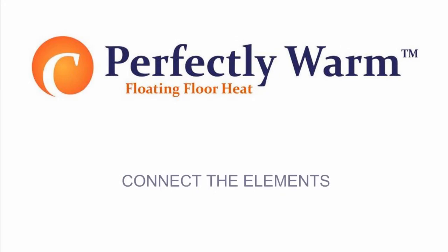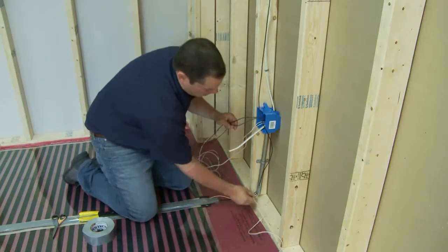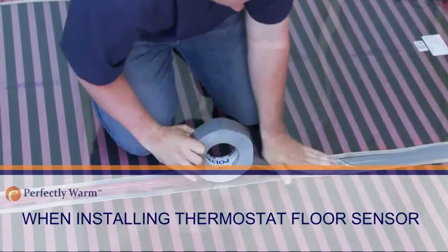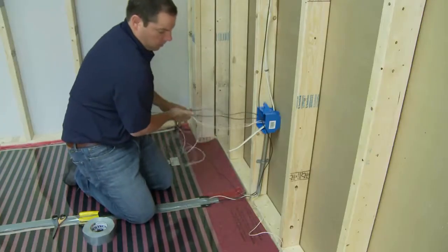4. Connect the elements. 5. Route the wires to the junction box provided for the thermostat. 6. Tape the floor sensor to the underlayment in an area at least 2 inches from any heated black part of the heating panel. 7. Route the sensor lead to the thermostat junction box.